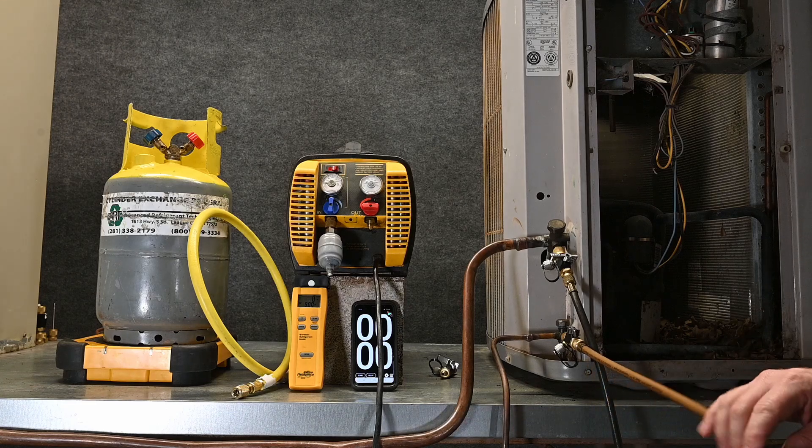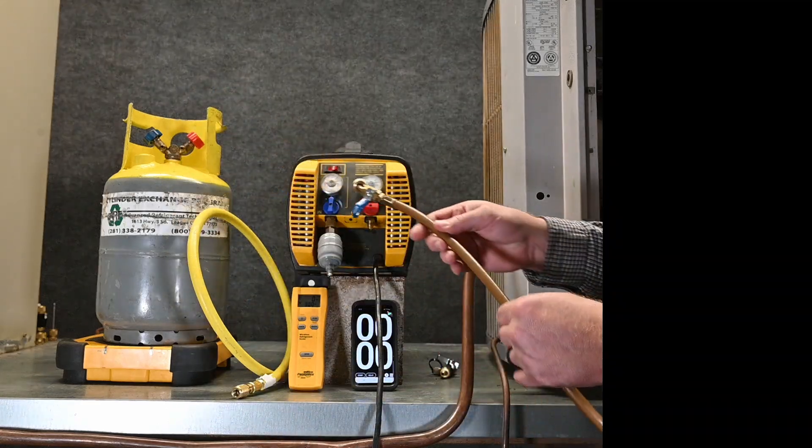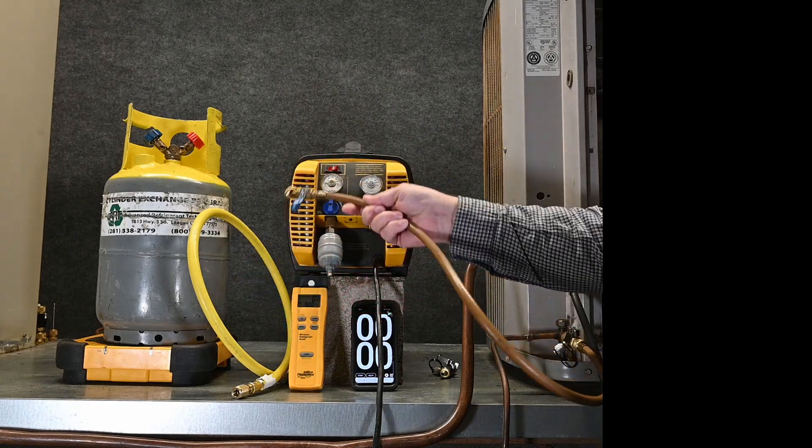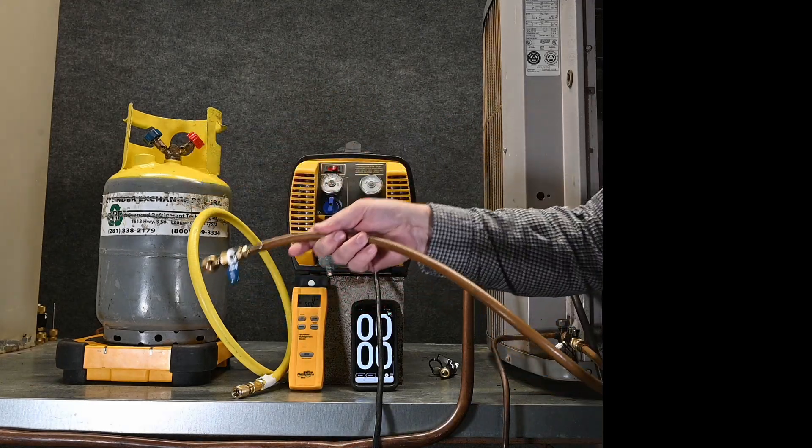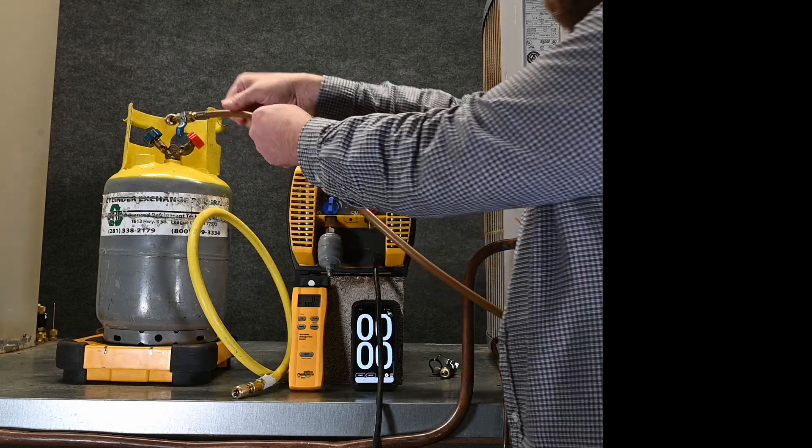So what we're going to do is take our liquid line, our high-pressure liquid side, and hook it up to the liquid on the tank. Now we could turn the tank upside down and hook it to the vapor port, or in this case we're just simply going to hook it up to that straw or dip tube.